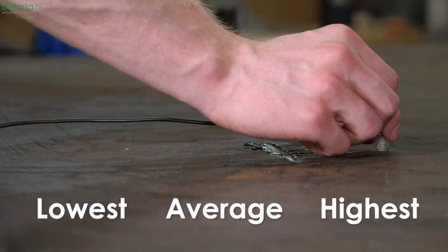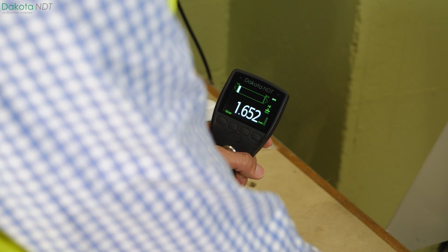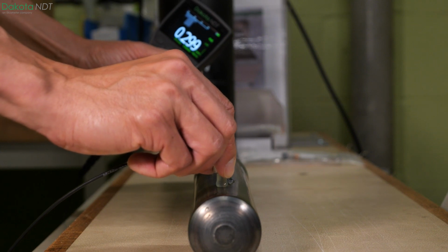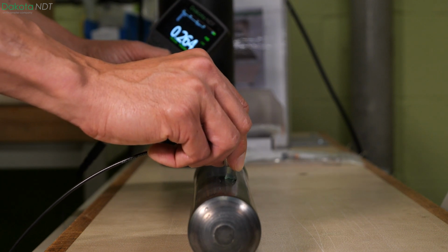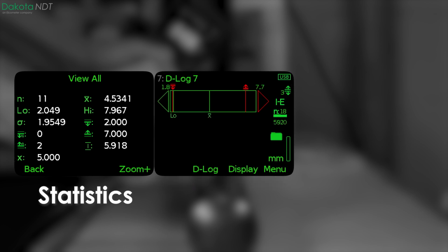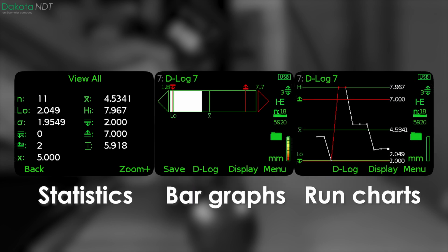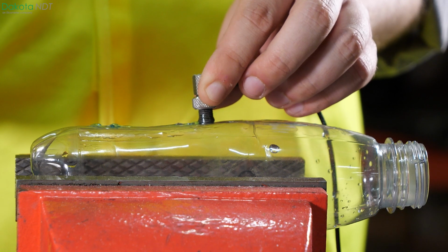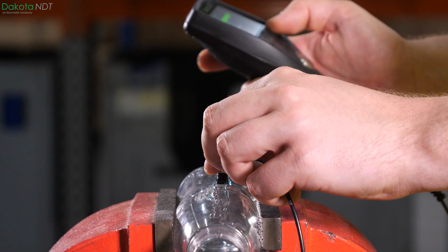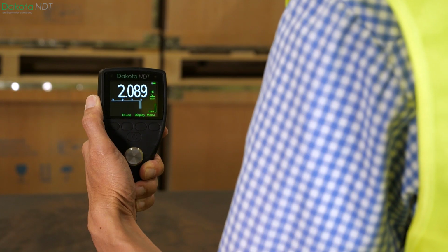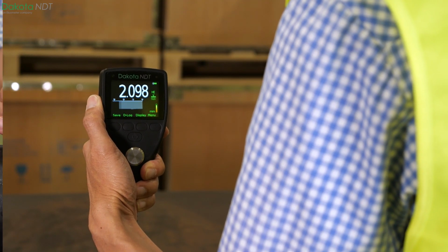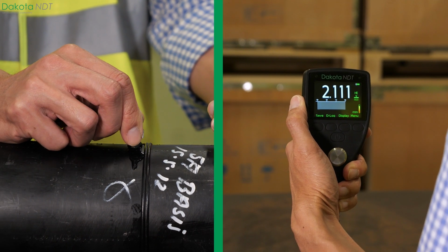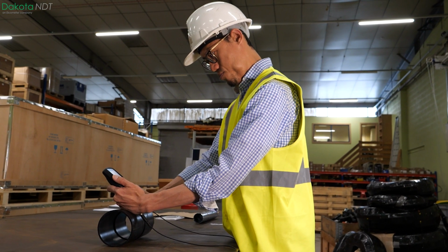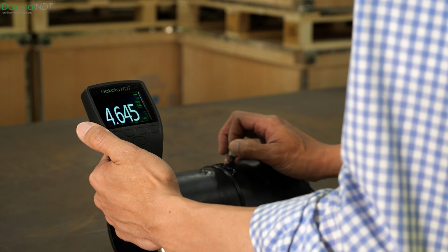In addition to displaying the material thickness, the DakotaNDT PCX8-DL has a choice of displays, which includes user-selectable statistics, thickness bar graphs, and run charts. The DakotaNDT PCX8-DL is also equipped with time-based thickness B-scan mode, which shows any changes in the material thickness visually as you move the transducer across the surface, making it ideal for quickly identifying large changes in depth within the material.